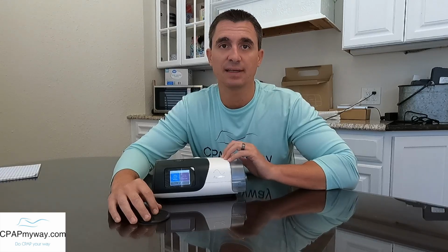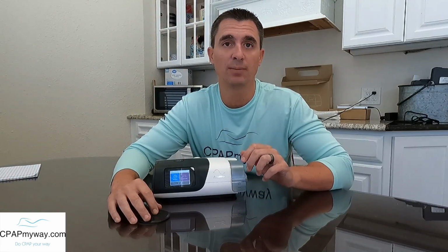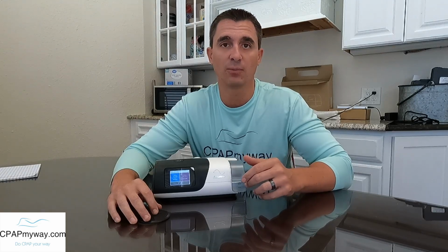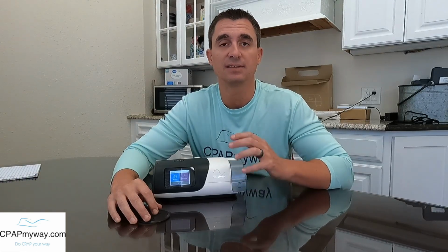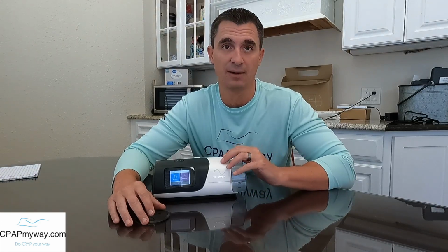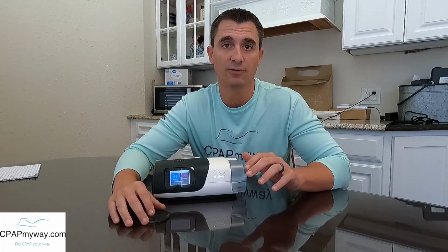Now, if your humidifier is not functioning correctly, almost all of the modern CPAPs will alarm or send you an error code somewhere to help you understand that it's not working correctly, right? You'll either get a beep, some kind of flashing light, or it'll distinctly say humidifier malfunction. Almost always you will see some sort of alert. So you can rest assured that if it's not working, you probably will be notified.